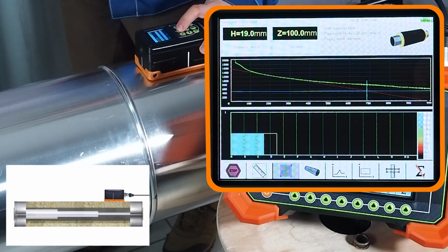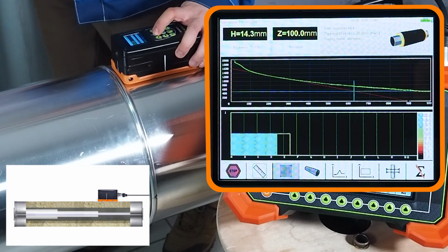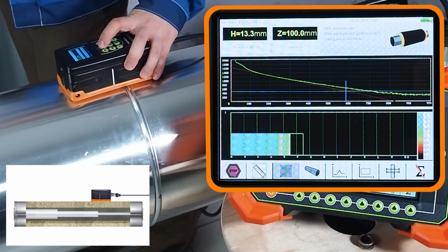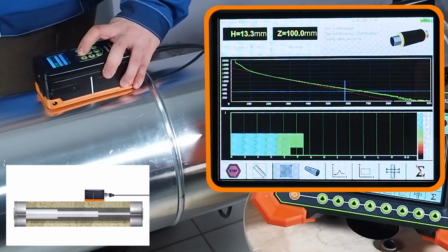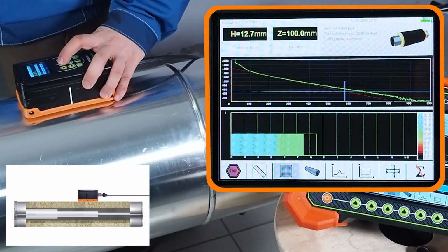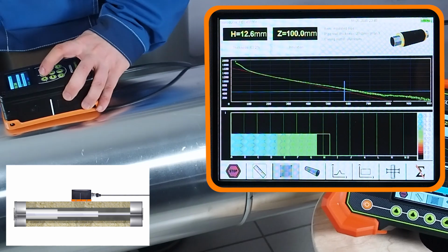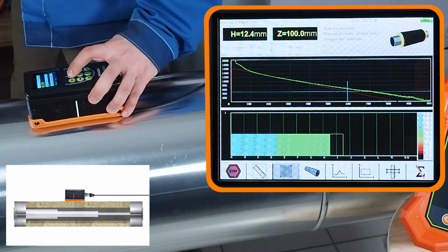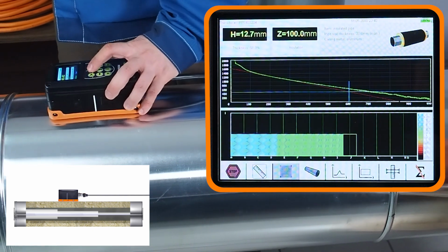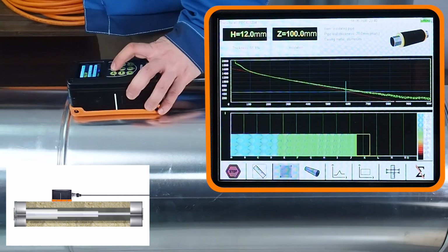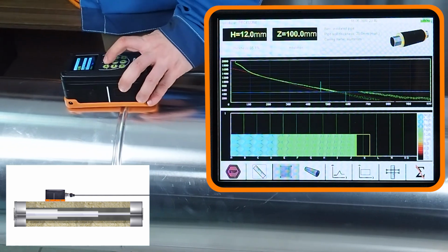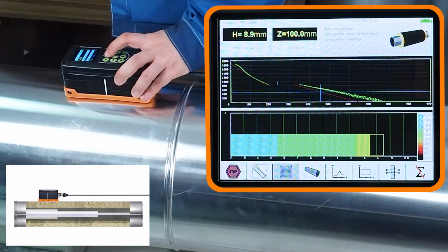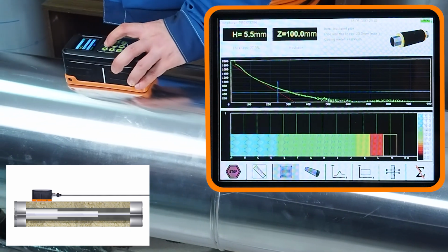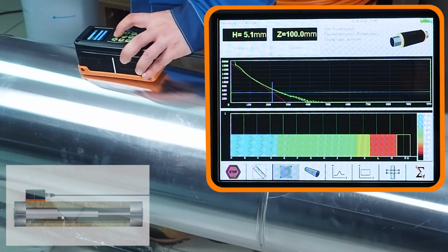The device detected 3 sections with different wall thicknesses. That corresponds to real situation, although it significantly smoothed out the areas of stepwise changes in thickness. This is the expected result, since the magnetized area of the pipe that affects the measurements at the current point is comparable and even slightly larger in size than the sensor. The purpose of the device is to detect large corrosion spots under a thick layer of insulation.